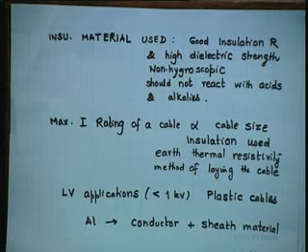Many places. Aluminium is of course getting more and more popular, as you know, for a variety of reasons. One thing is it is cheaper, it is lighter, and we produce aluminium more than copper in India. But aluminium has a lower current density than copper. 2.1 is copper and 1.2 is aluminium. That is enough, but the weight ratio is too much.